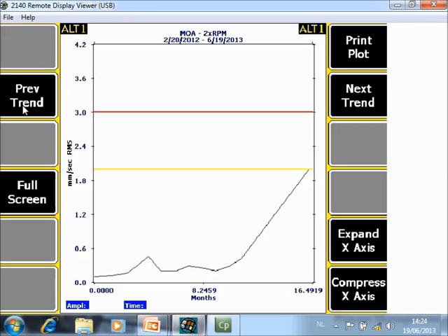I give you one example. On a certain point, you measure a very high value. Then maybe it's very useful information in the field to know that this high value is new, or maybe something that is already on the machine for the last 2 years. If it's already been like that for the last 2 years, maybe you will act differently than when the value is brand new. So this is a strong analysis tool in the field.